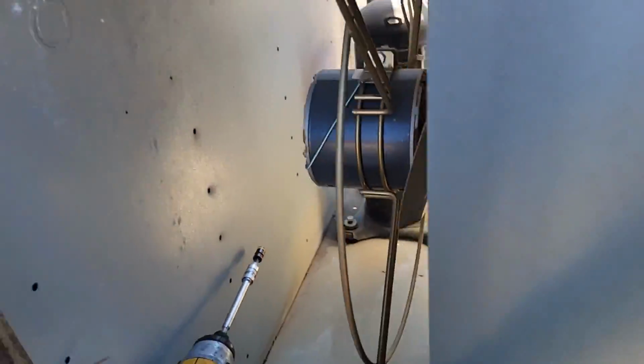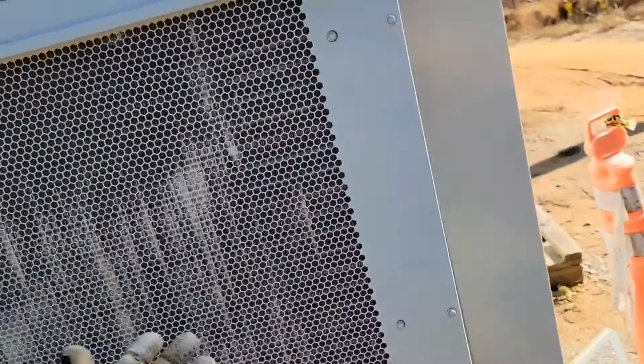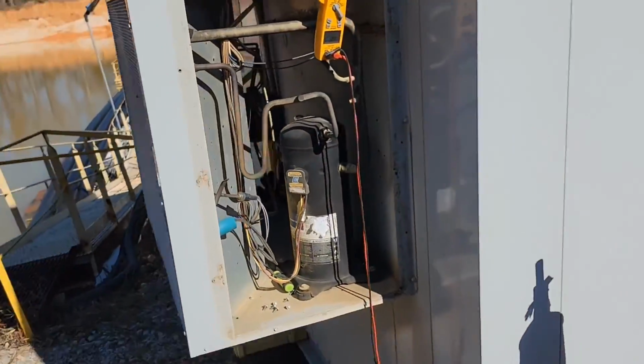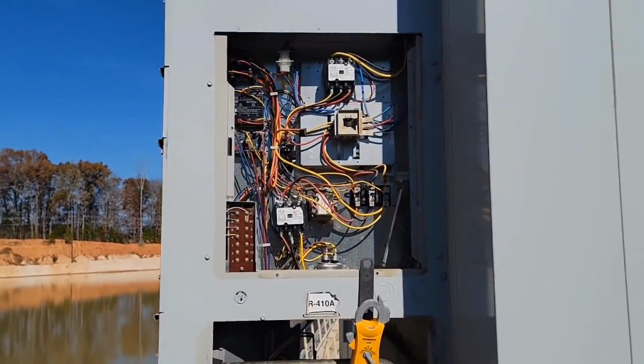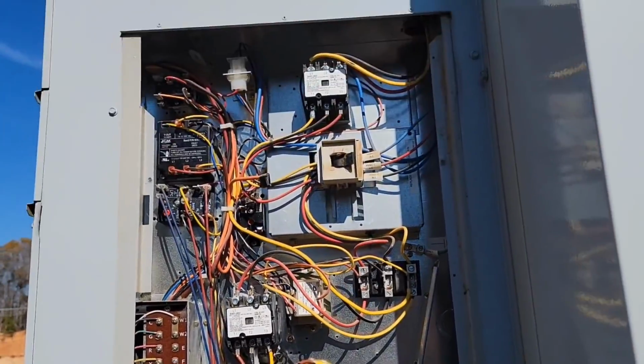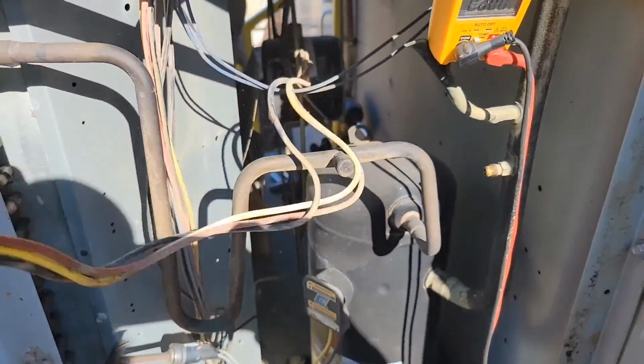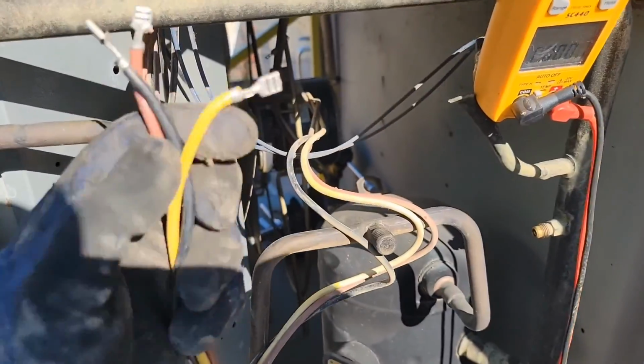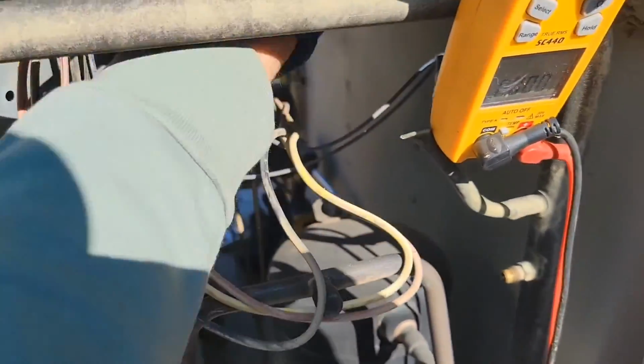It's likely the bearings are bad because I did check the capacitor. If you don't know how to check a capacitor, just check out my playlist, HVAC Tips for Technicians. I have a video. The outdoor fan motor is not 3-phase, it is single phase. We got a yellow, a black, and a brown wire.